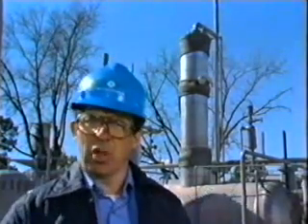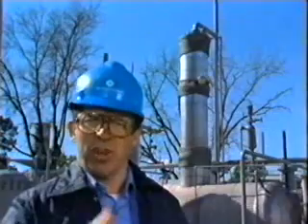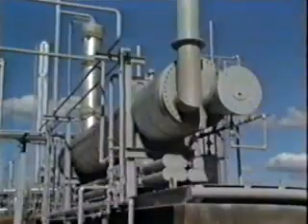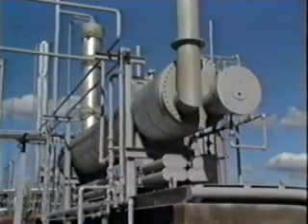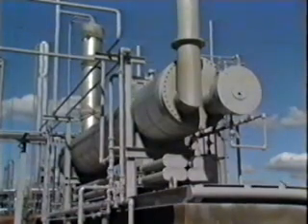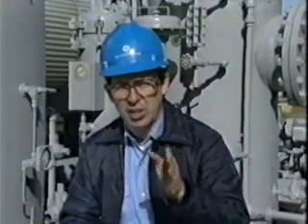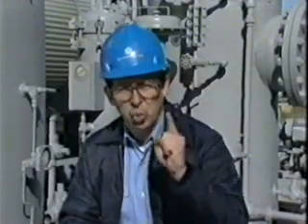Low still overhead temperature can cause reboiler overload and excessive fuel consumption. High still overhead temperature can cause glycol loss due to vaporization. Now let's look at operating pressures in the contactor, regenerator, filters, and GCG separator. If you operate the contactor below the proper design pressure, you will have problems.